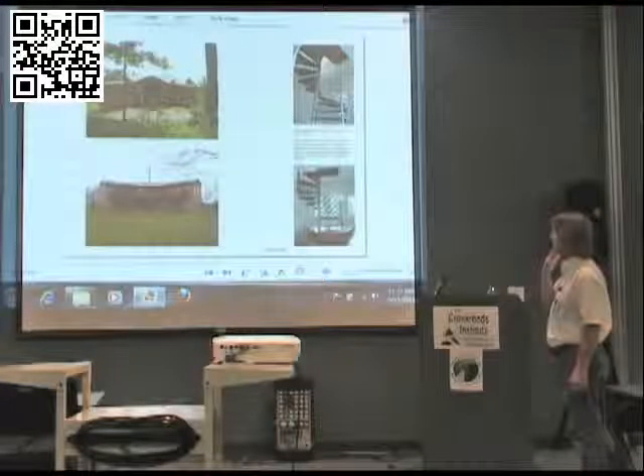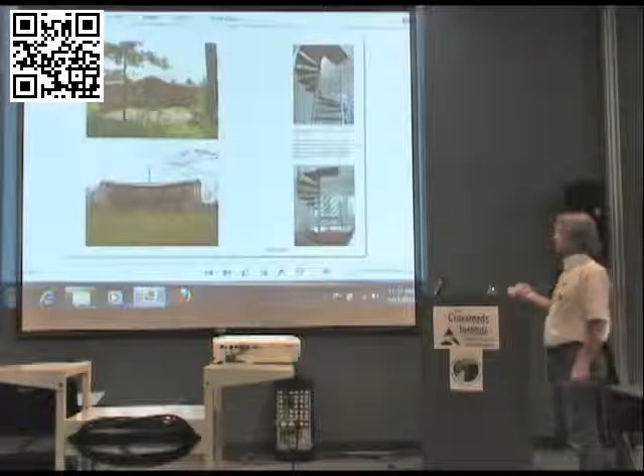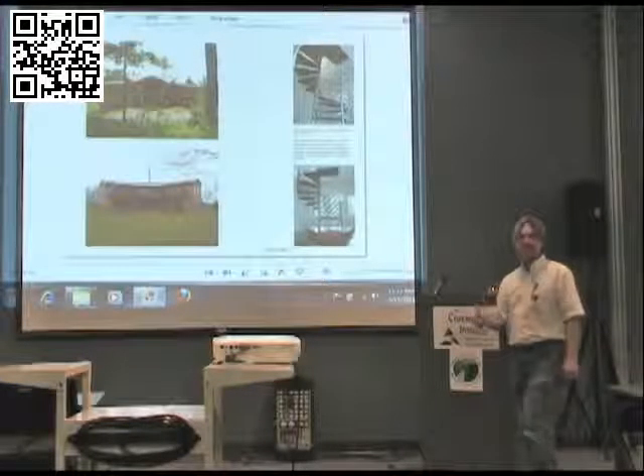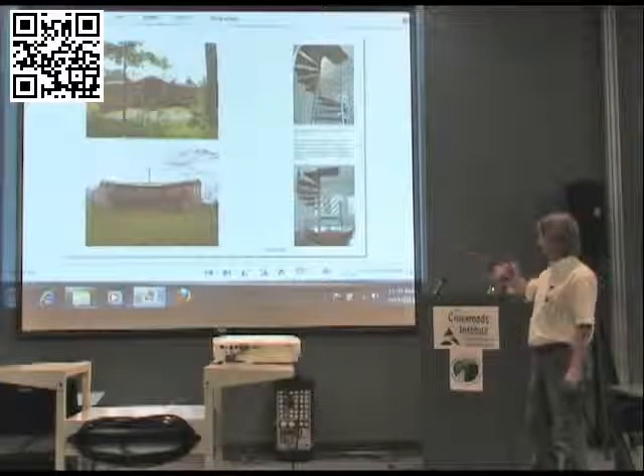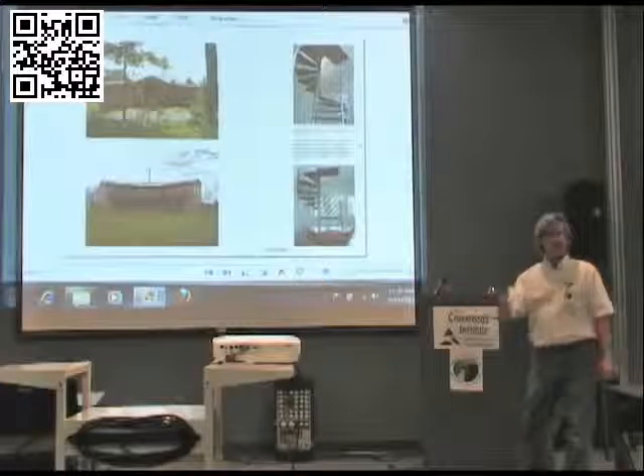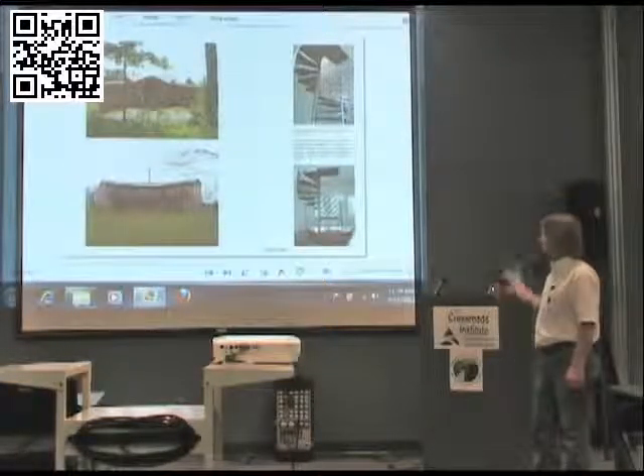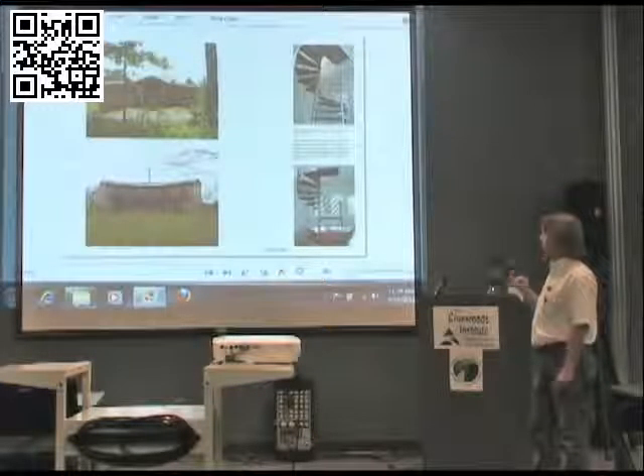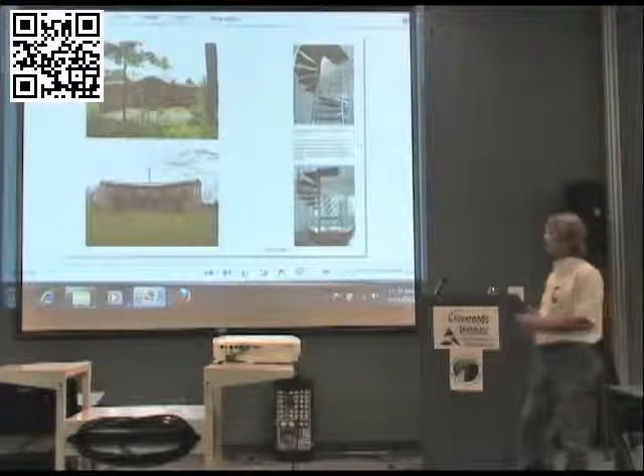It almost looks like two different houses, but in the backyard we did geothermal, which, depending upon your situation, can be a viable way to provide heated hot water for your house. This particular one has a network of pipes buried 5 feet underground, below frost, that circulates back through a geothermal heat pump for heating and cooling the house. You can also do that by drilling wells if you have a small site or it's constricted.